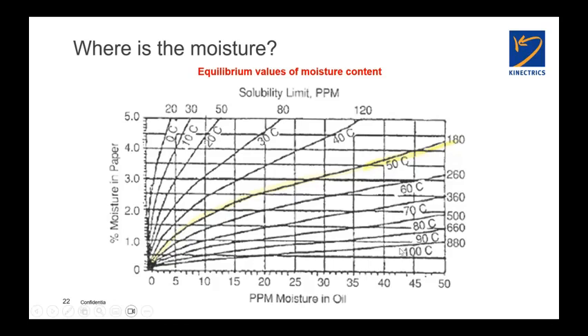So if you were to take a case of a transformer operating, well, let's just pick the bottom one because it's easy. It's almost linear, 100 degrees C. If I have 20 parts per million of moisture in the oil, I can look across and I see my moisture content in the paper is about 0.5%. Okay. If I now look at room temperature, look what happens. Water content in the oil of only 10 parts per million at 20 degrees C. So now I'm coming up here and coming across, it infers 4.5% moisture content in the paper.